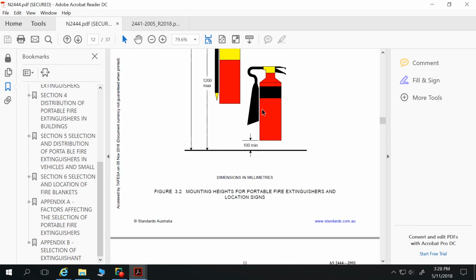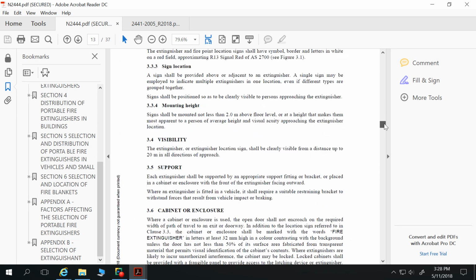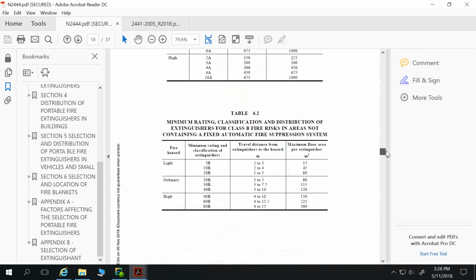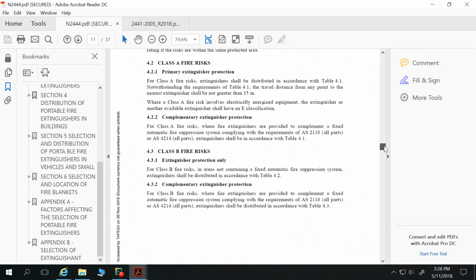Actually, what we've got in here is 4.2.1. I'll just go through that as well. Because we've got fire hose reels and separate fire compartmentalisation, we're fairly sure that we don't need to worry about these. But for instances where we don't have these fire hose reels, we are required to have quite a few fire extinguishers mounted about the place, so it's important to know this stuff. So, 4.2.1, primary extinguisher protection.